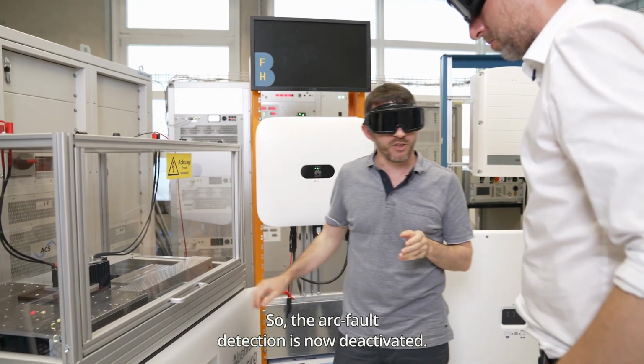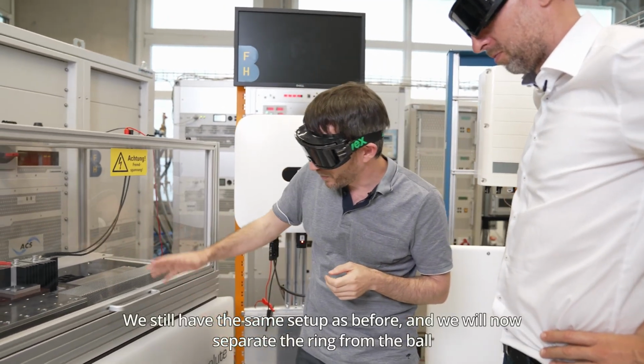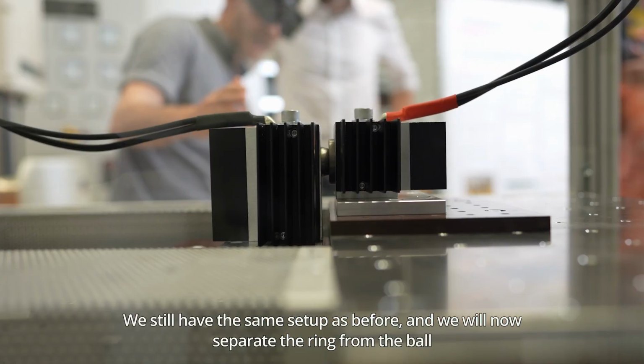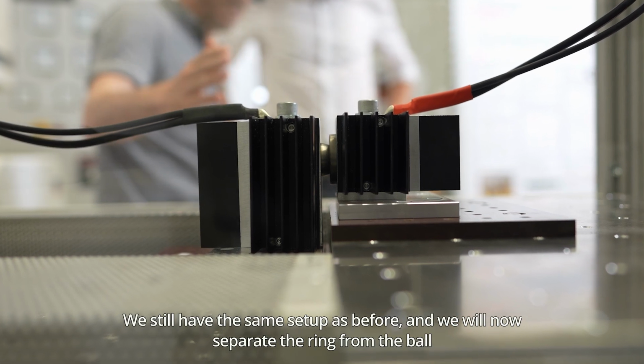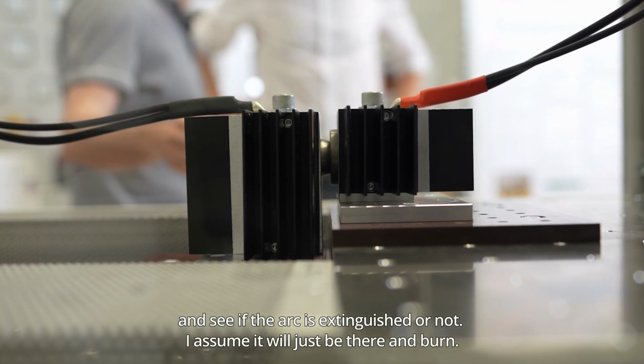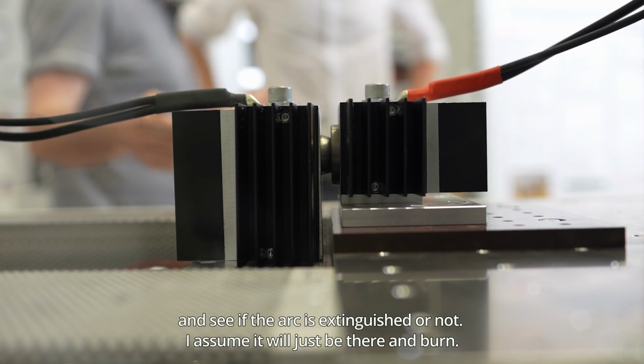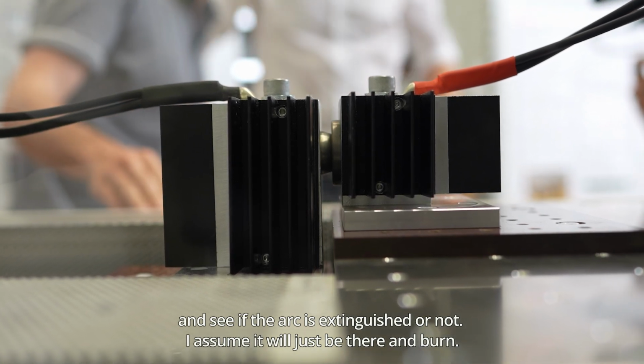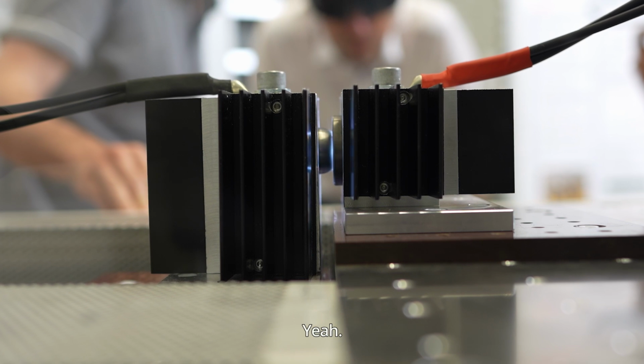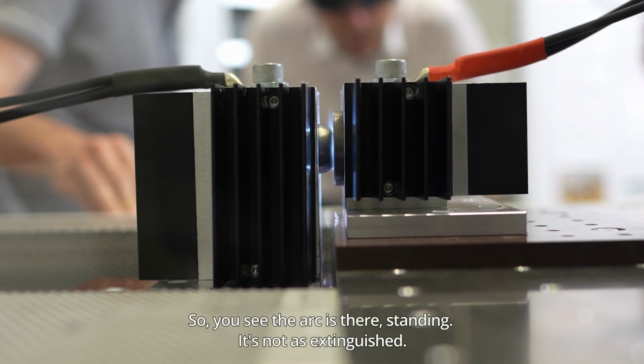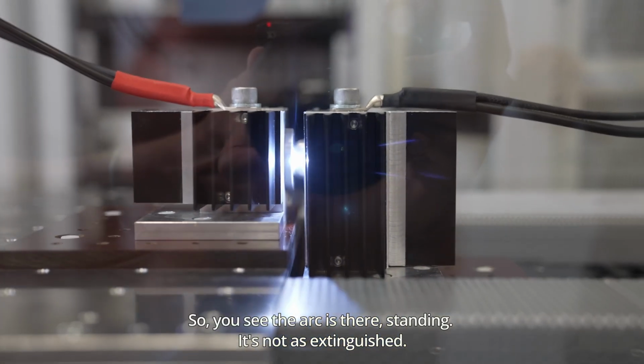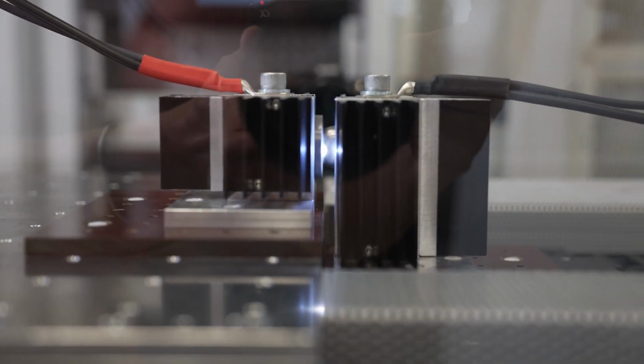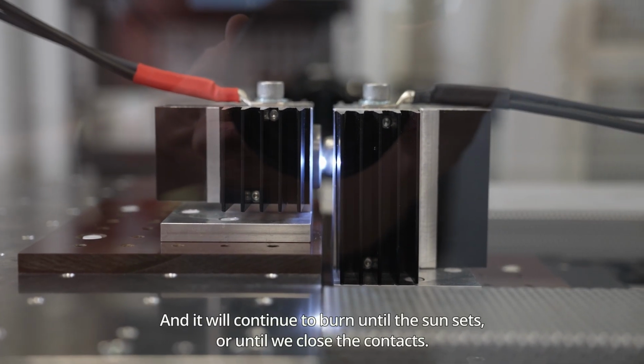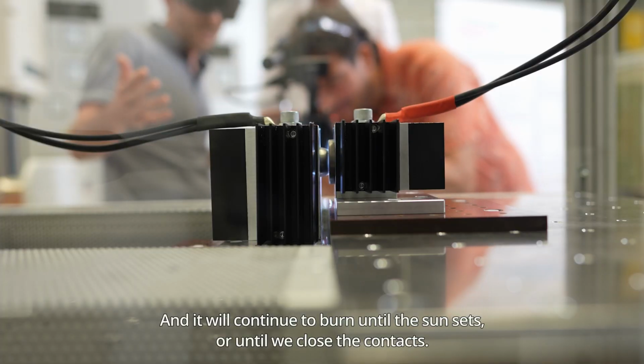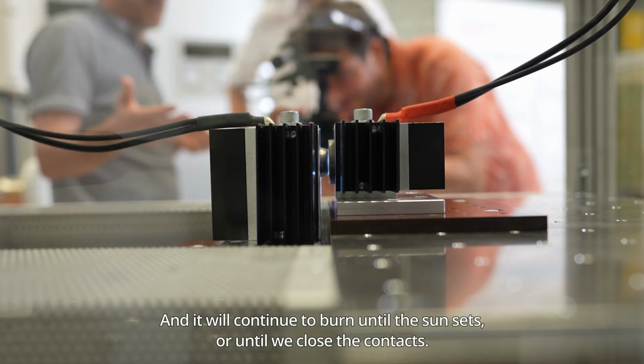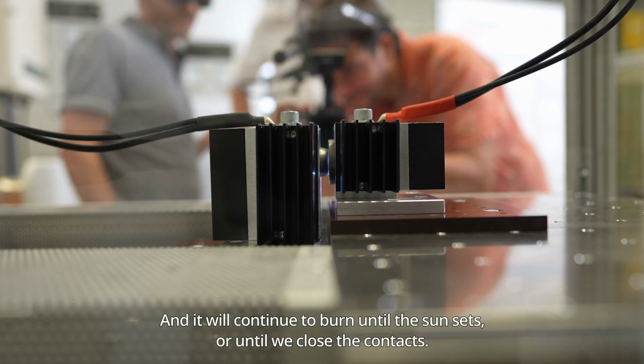So the arc fault detection is now deactivated. We still have the same setup as before, and we will now separate the ring from the ball and see if the arc is extinguished or not. I assume it will just be there and burn. Yeah. So you see the arc is there standing, it's not extinguished, and it will continue to burn until the sun sets or until we close the contacts.